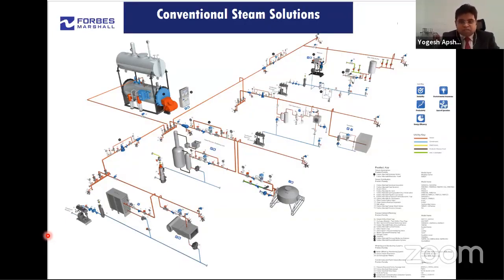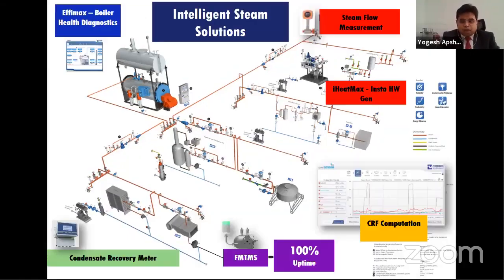So what is the difference between the conventional steam system and the intelligent steam system? This is how we define the intelligent steam system, where there is an interface between the hardware and the software. Whatever data we are monitoring on the devices, we can compute on a piece of software and analyze together. Like for the boiler, the boiler health diagnostics, such as the steam flow meter, gas flow meter, or diesel flow meter in the boiler. Then the steam flow metering, plant-wise and equipment-wise. Then the instant hot water generation.